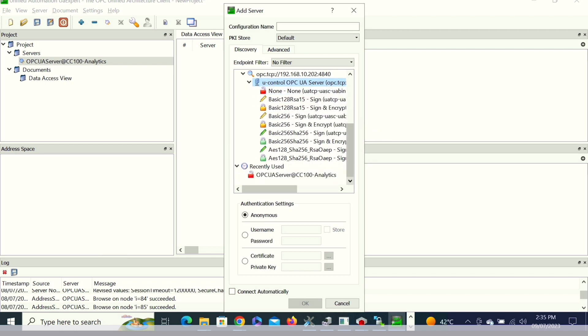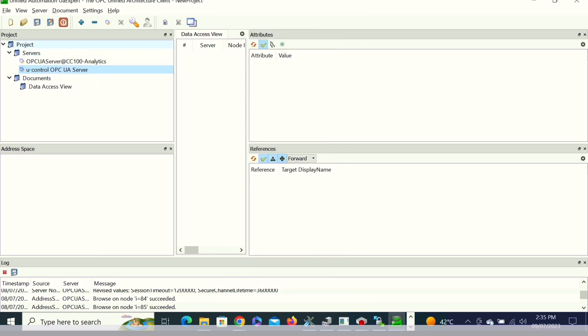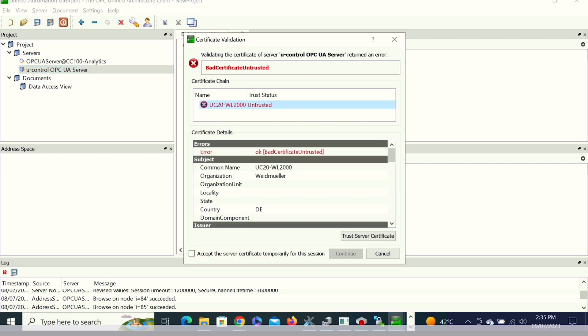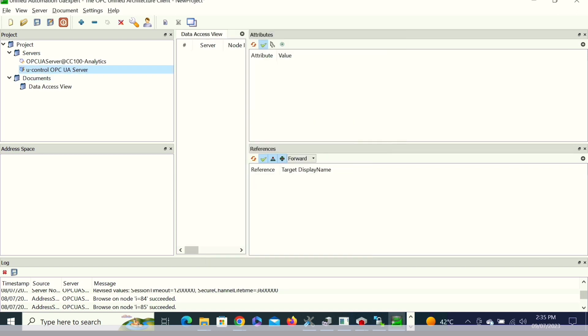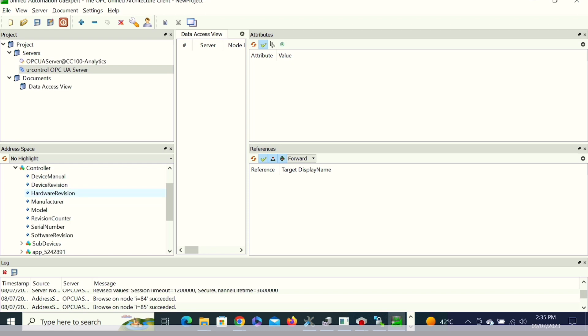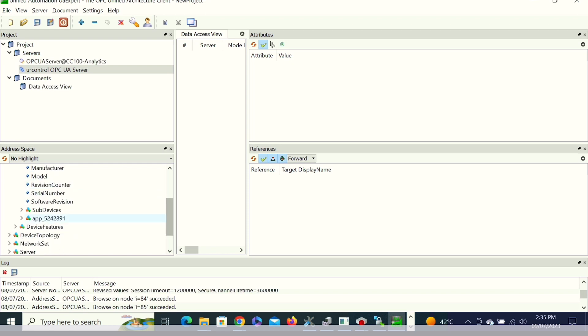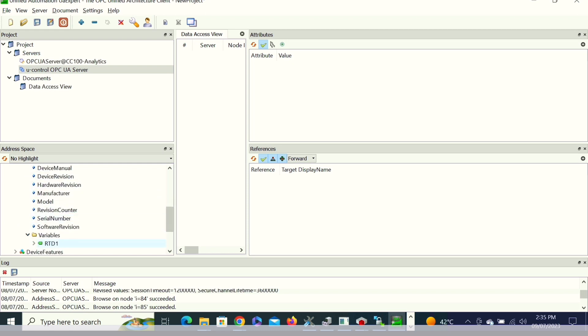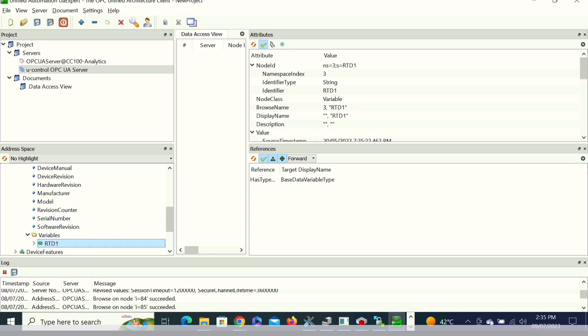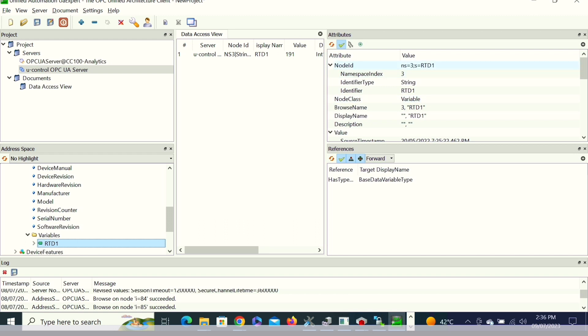The PLC is having OPC UA server and we are using UaExpert as a client. Once we configure it in the UaExpert and connect, then we need to trust the certificate. We can see that it is connected and inside the structure, we will go to the RTD. When we drag and drop it, we can see the value here. In this way, in this particular PLC, we can even configure the OPC UA server and client model.